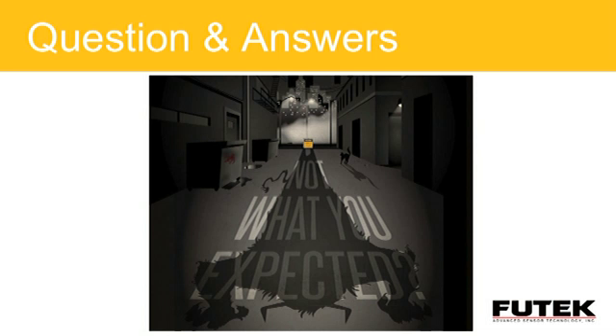That's a tricky question, mainly because our standard recommendation for an NIST traceable calibration is 1 year. That's something we set up, but it's really up to the customer. How critical is the application they're doing? Should they be verifying every 3 months? Is this product used with high cycles, potential for abuse or overload, or could the sensor be dropped or handled roughly? I think you want that sense of assurance that the part is meeting your requirements.